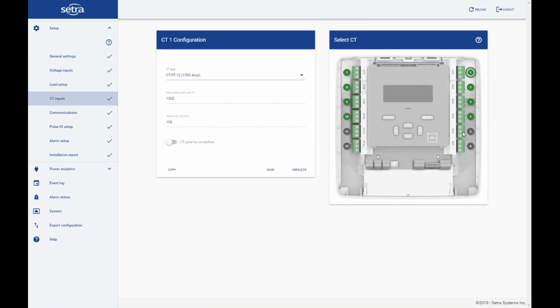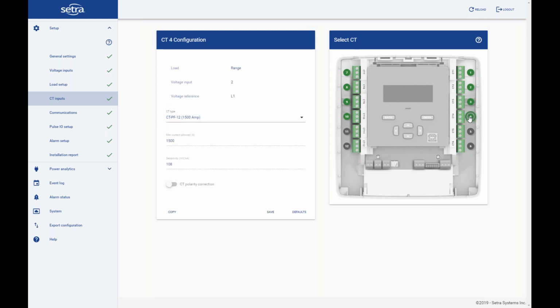On the CT inputs, this is a 12 load meter, so you can see the 12 CT inputs, and you can click on the CT inputs and see the information of how they're tied. You can see the drop down for the CT type, so the CT PF12, which is a Rogowski coil part number, and all the parameters are configured here within that meter. You can also correct the polarity of the CT. So if you find out later that one was installed backwards and you were getting negative energy readings and power readings, you can come in here and flip the CT correction without having to go back into that panel.